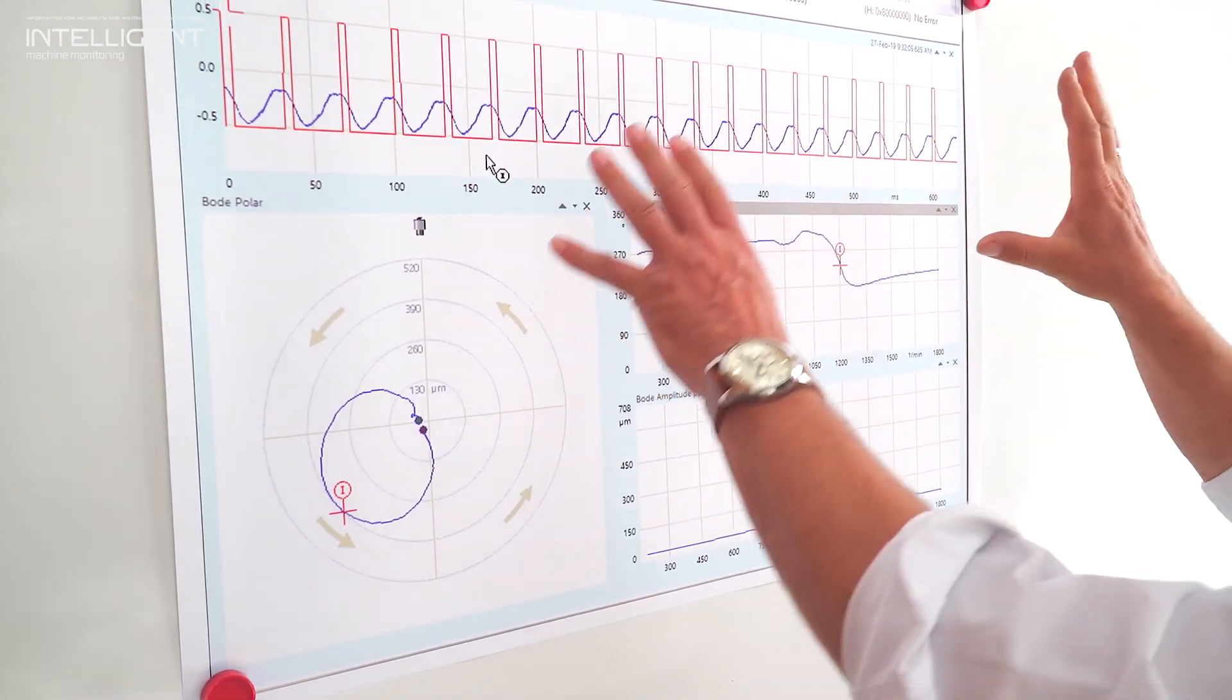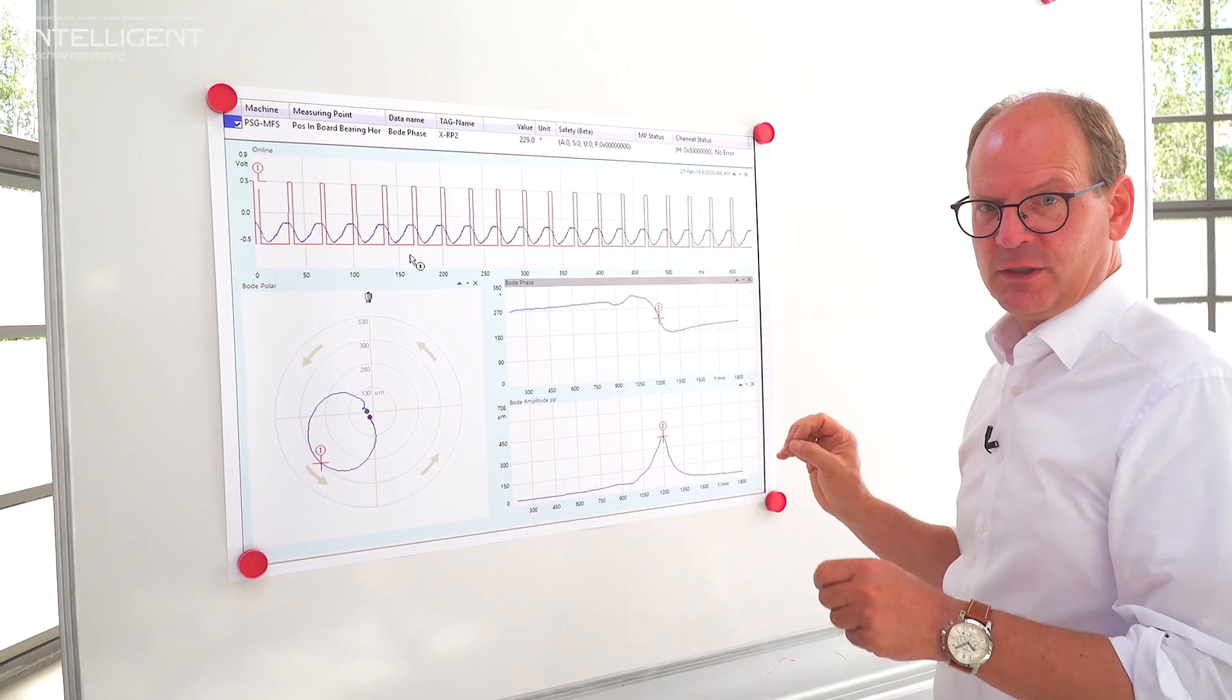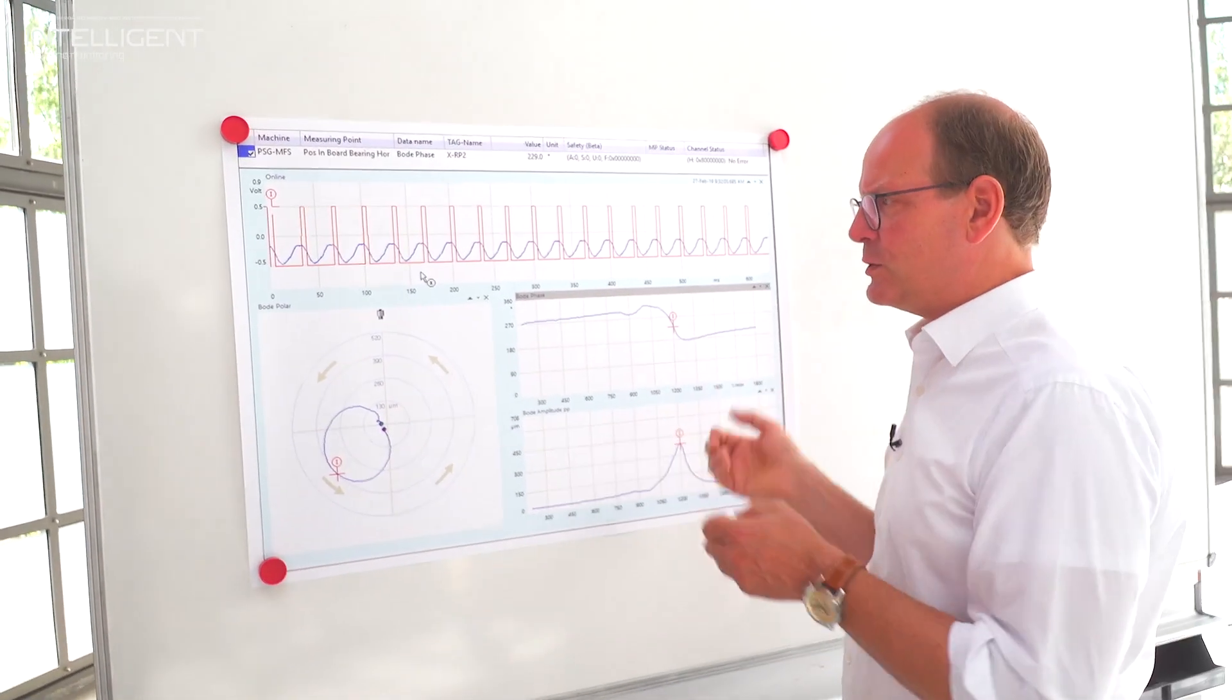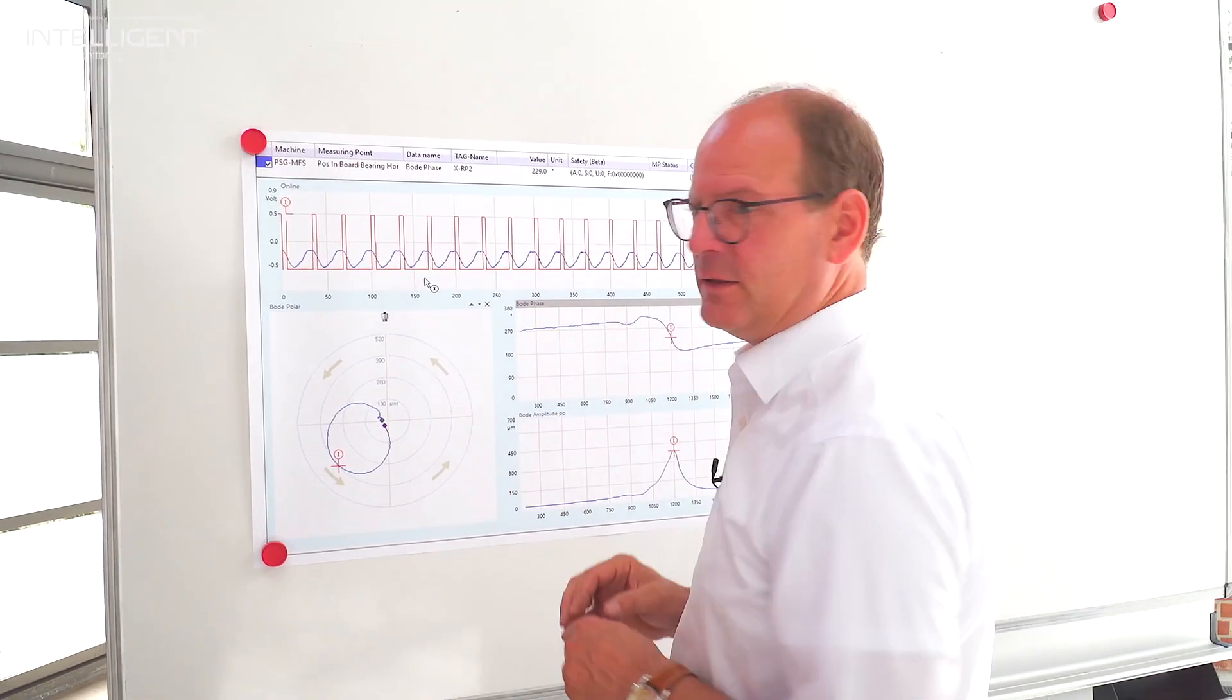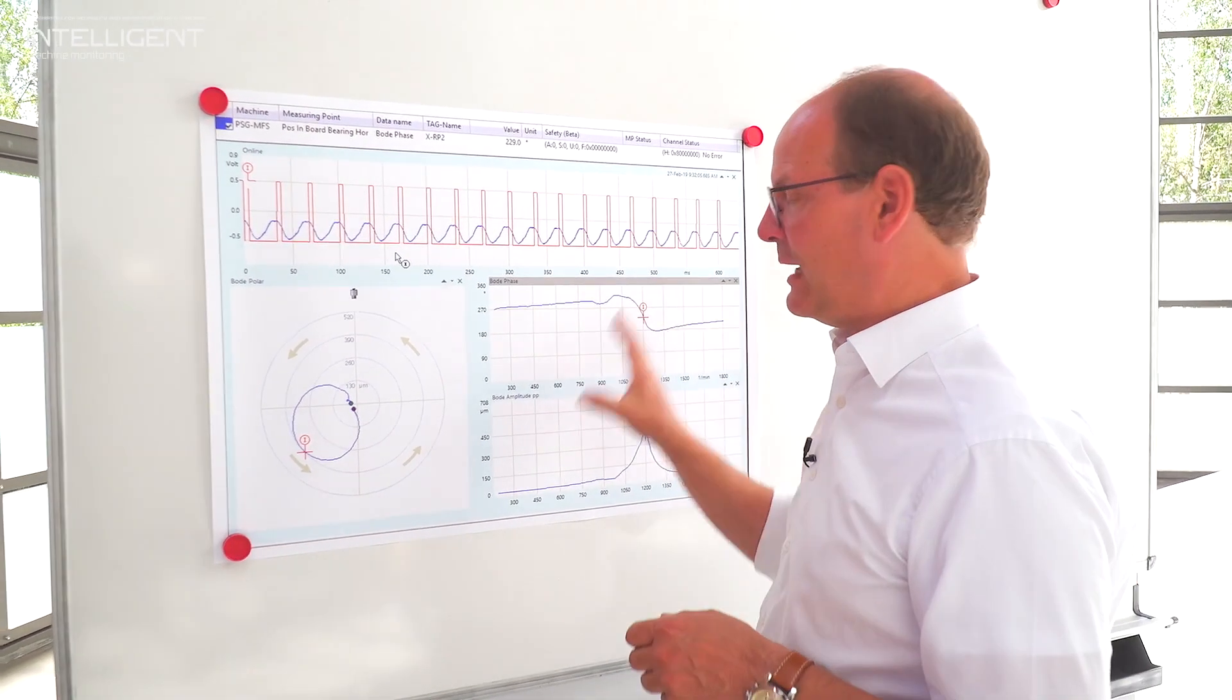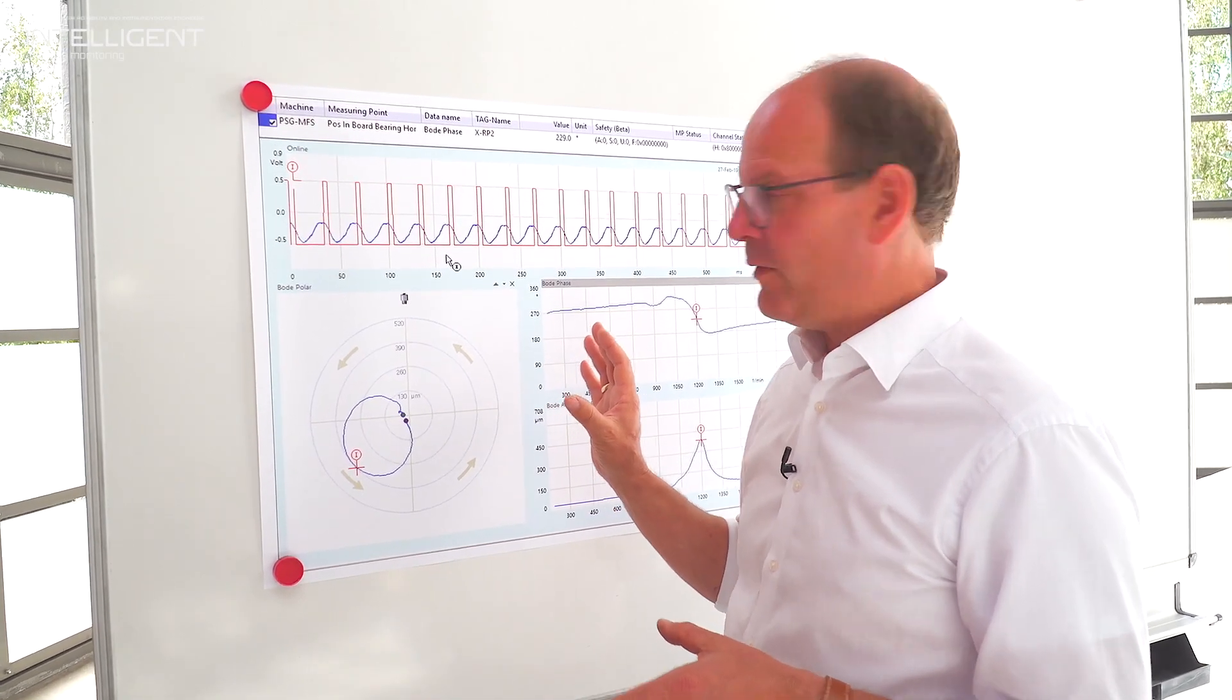This is really a very important tool to monitor and detect changing conditions during the run-up and coast-down of the machine. It's also named run-up and coast-down analysis. It's a transient tool. This Bode Polar Plot will start automatically by every start-stop or safety limit violation of the machine.